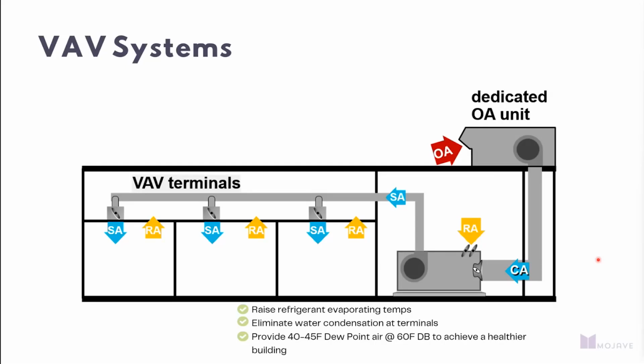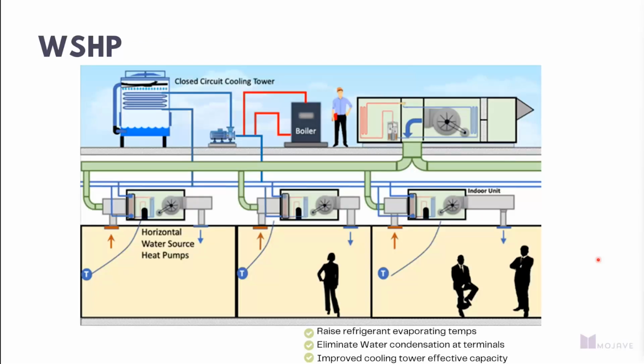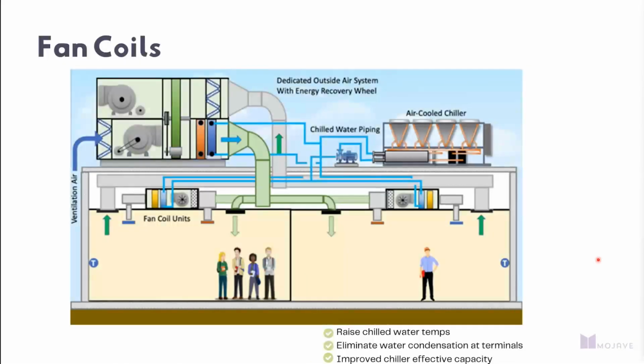Now, a couple other ways this is being applied, specifically Mojave, and with respect to these different systems I've gone through. Mojave units have been used to pre-treat rooftop units in a style like this. Additionally, we have been using our system to dehumidify chilled water systems. And what that means is we're drying out the air being delivered to coils on water source heat pumps or fan coils, drying out that coil to where they're not handling any latent anymore, and doing just pure sensible cooling, similar to what a chilled beam system would do.